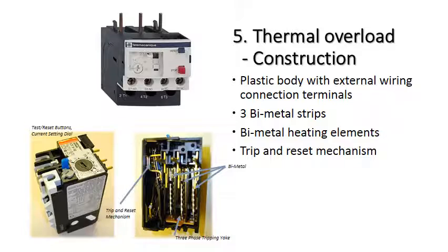Then we have a similar sort of thing, a thermal overload. It just works slightly differently. It has different advantages and disadvantages. It has, once again, a plastic body with external connections on it. It has three bimetal strips and heating elements for those strips. It also has a trip mechanism that when one or more of the bimetal strips bends, the mechanism is tripped and the contacts open or close.